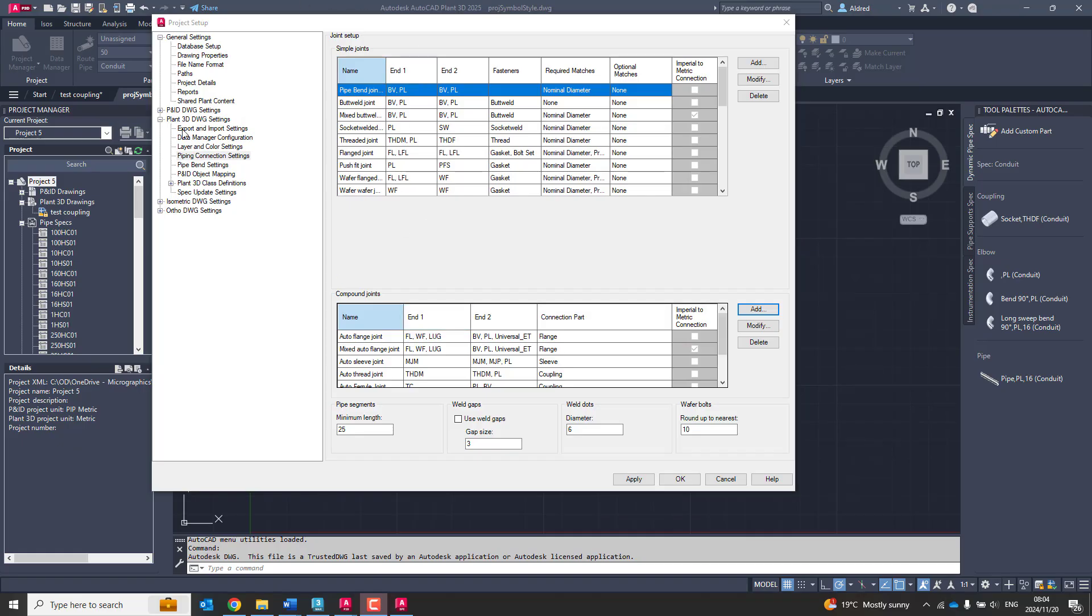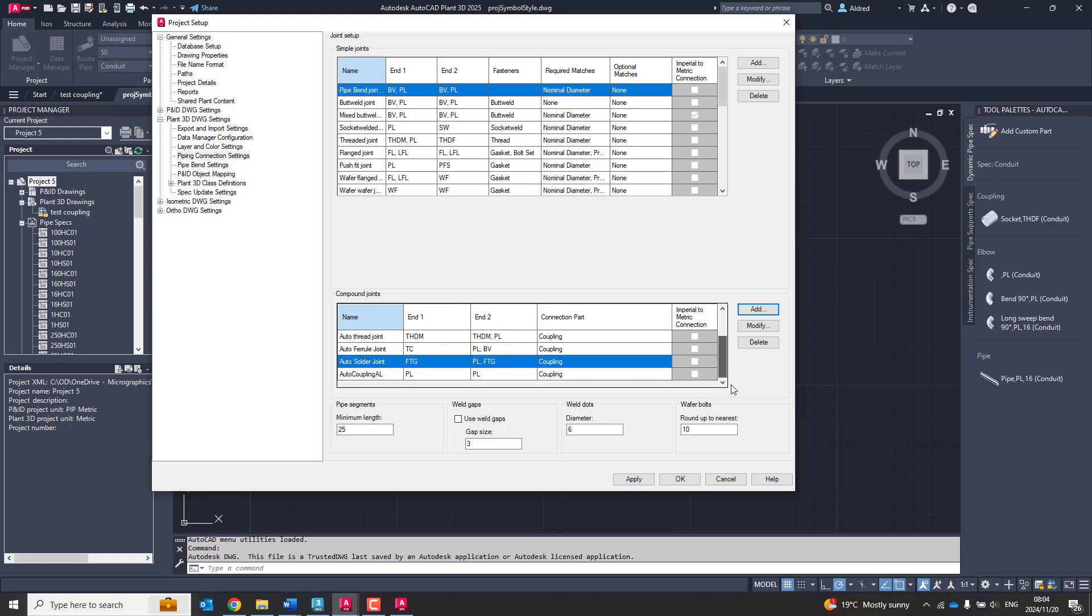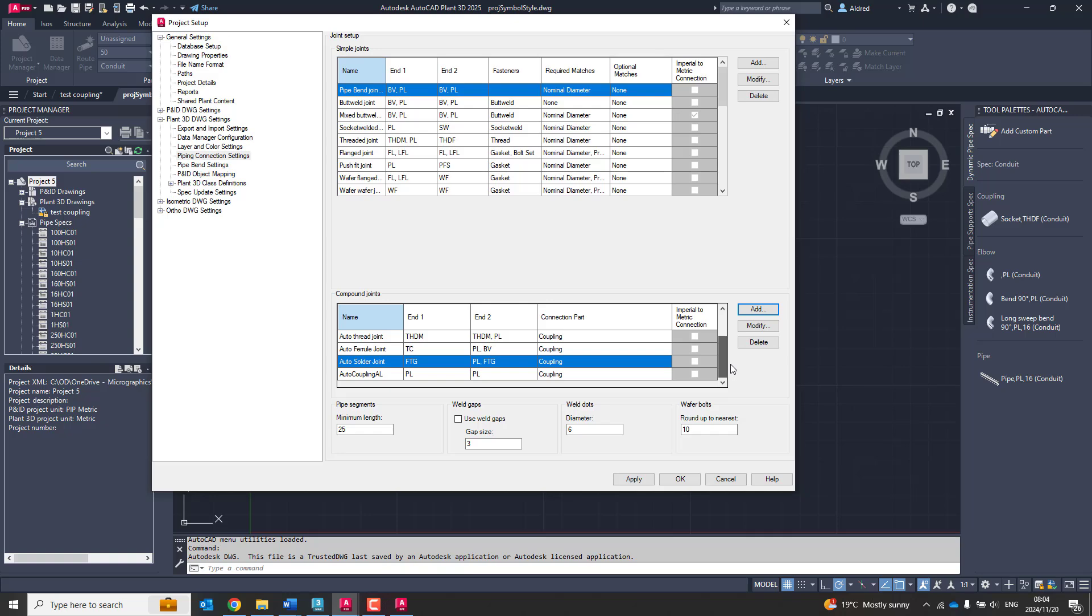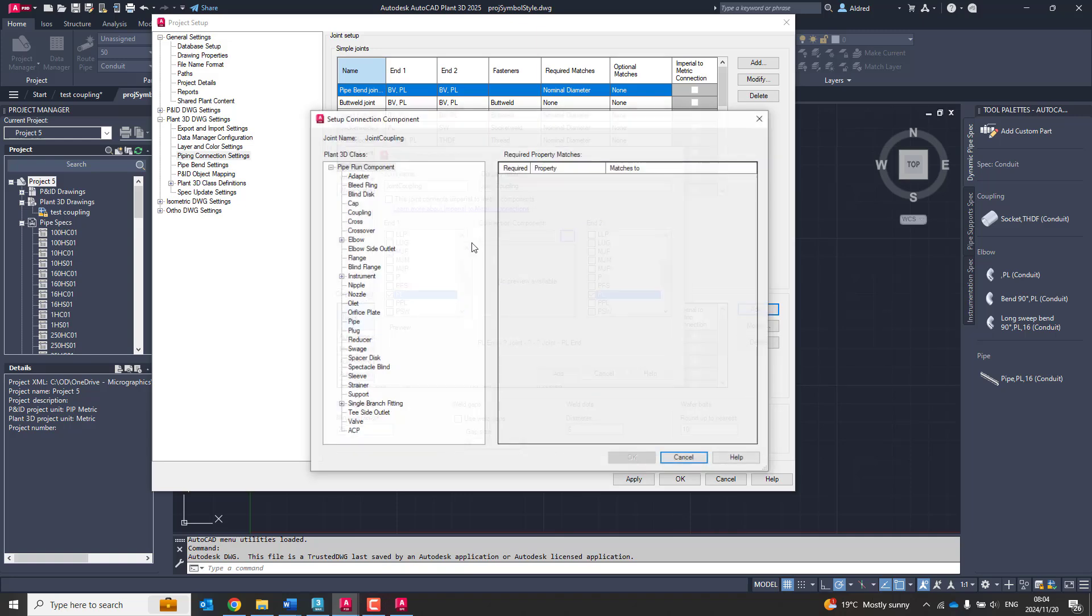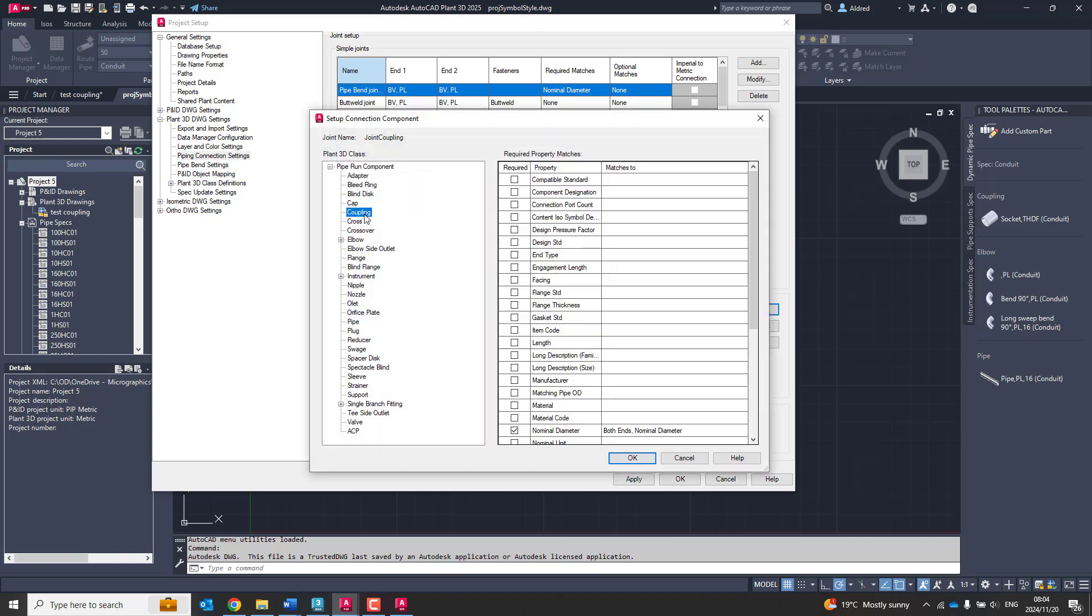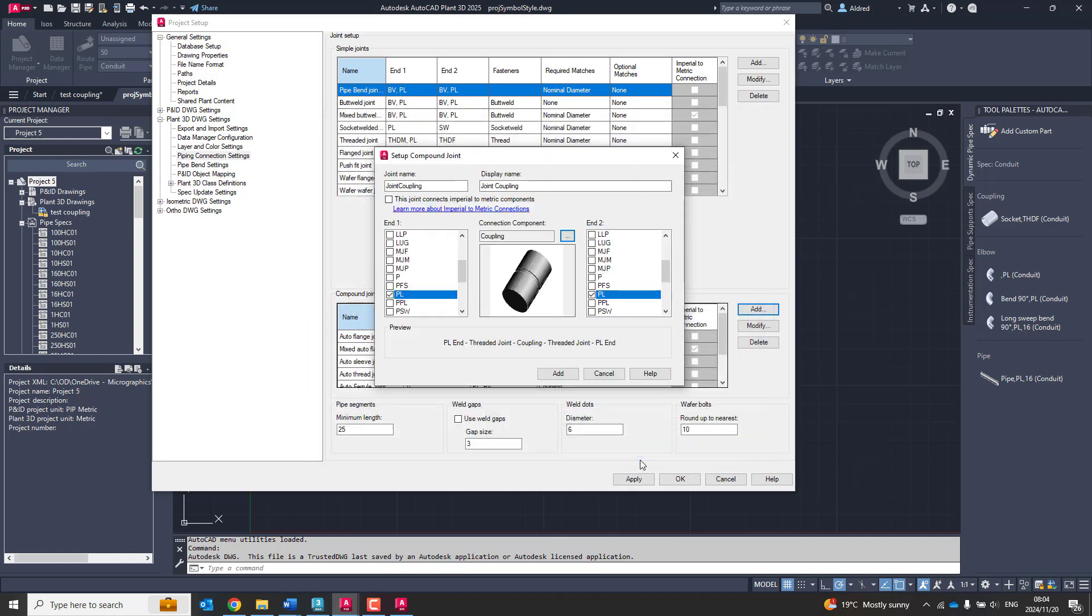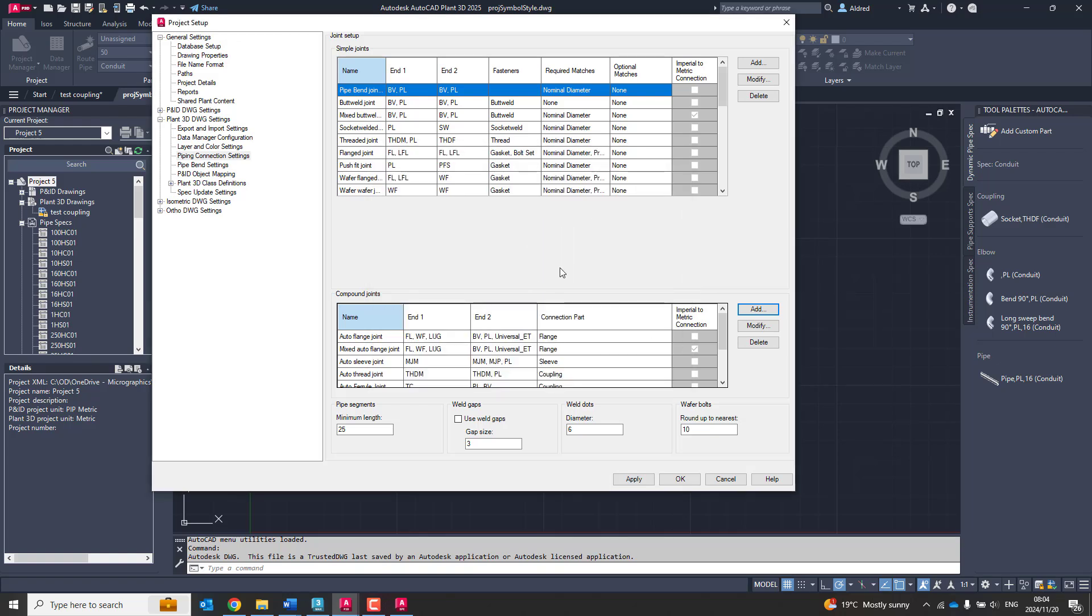So remember we had the PL on the pipe side and we had the threaded female. So in the project setup, we're going to go to our pipe connection settings, and what we're going to do is we're going to create a compound joint. So in the compound joint over here, I am going to create a new compound joint. Let's go to joint coupling. And on the one end connection, I want to have it as PL, so that's the pipe. And then on the other one, I want to have PL as well. And the connection component, I want it to be a coupling. And then add. Now what it does is it adds that joint coupling over there, and I can go again.